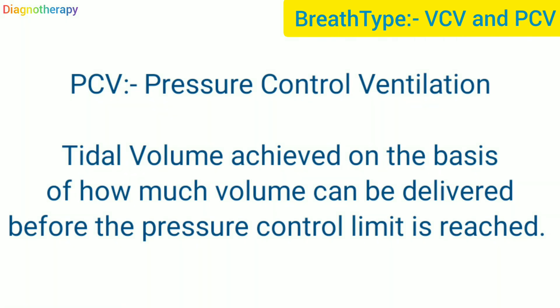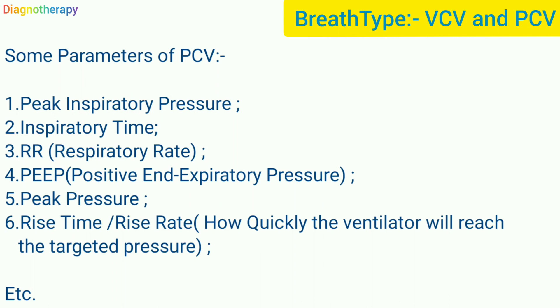In pressure control ventilation, the tidal volume is achieved on the basis of how much volume can be delivered before the pressure control limit is reached. Parameters include: peak inspiratory pressure, inspiratory time, respiratory rate, PEEP (positive end-expiratory pressure), peak pressure, and rise time or rise rate — that is, how quickly the ventilator reaches the targeted pressure. Other settings depend on the ventilator company and model, and terminology may differ slightly between ventilators.